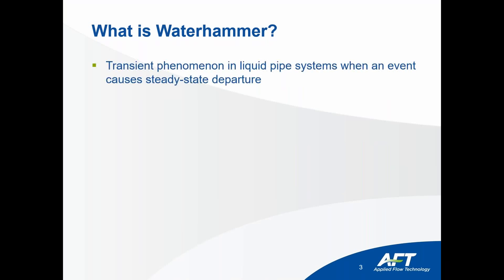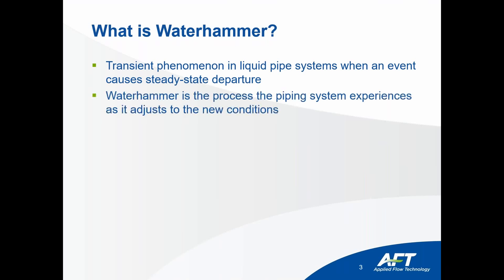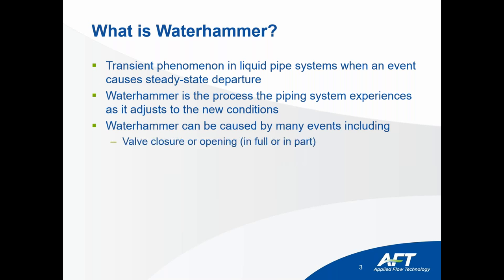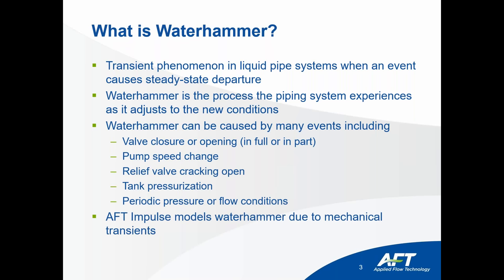What is water hammer? It's a transient phenomenon in liquid piping systems that causes a departure from steady-state operation — it's the process where your piping system is adjusting to new conditions. It can be caused by several different events like a valve closure, a pump turning on, relief valves or check valves popping open and closed. AFT Impulse models water hammer due to mechanical transients — any of those things where you have a device changing its operation.